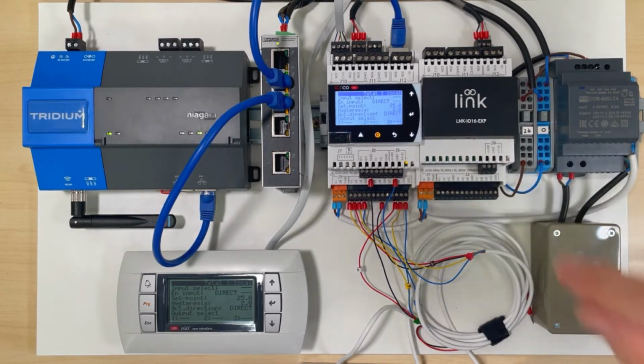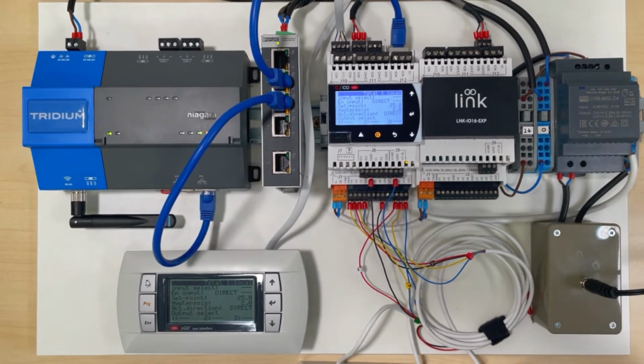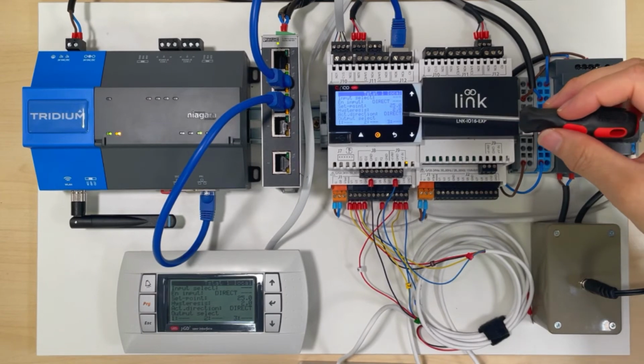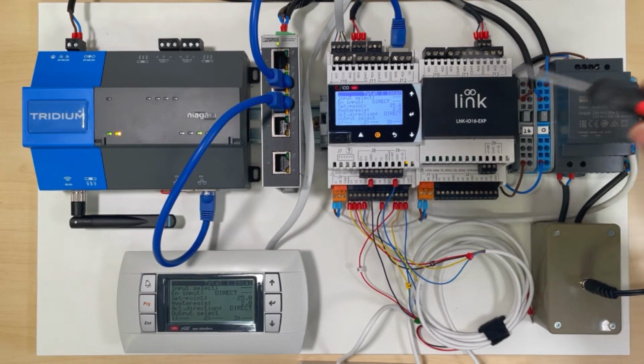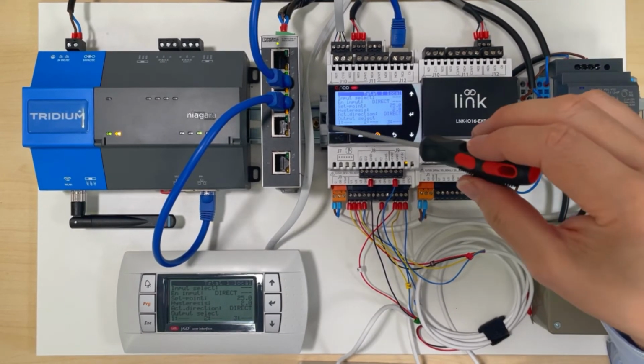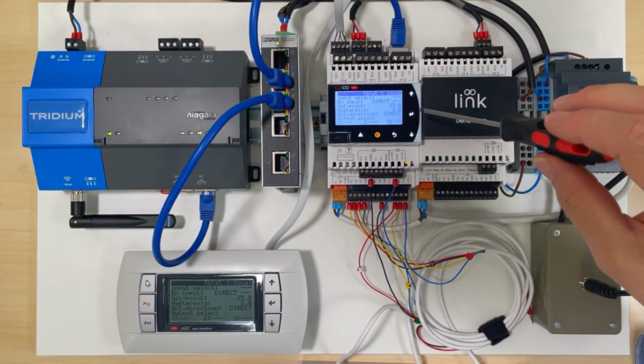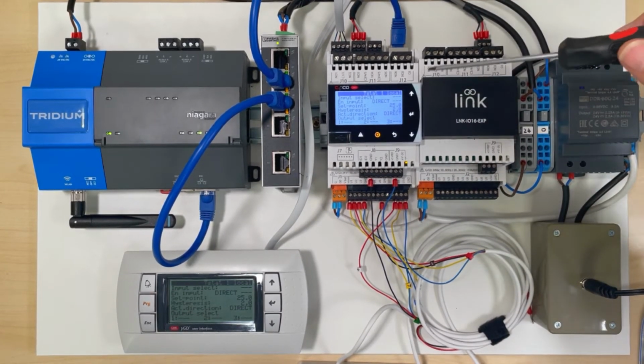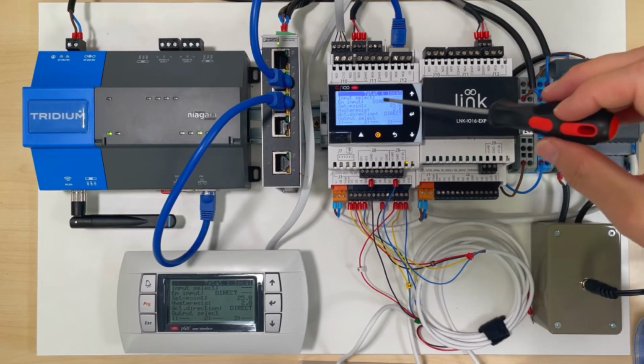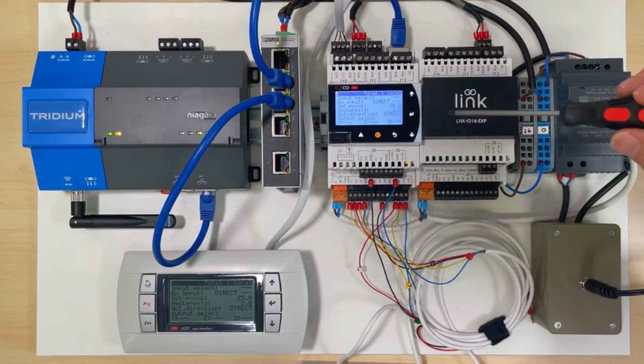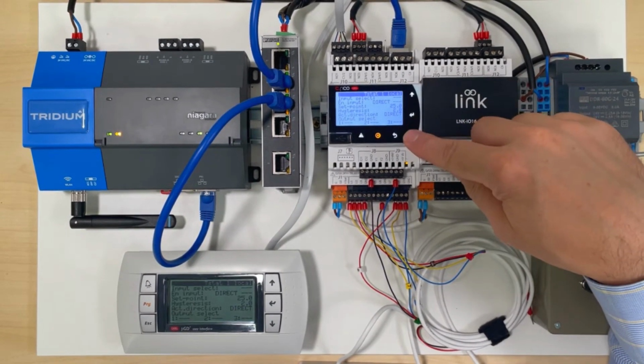Okay, there's a T-stat. So yeah, this is basic sort of thermostat action. As you can see here, you set a set point and hysteresis so it doesn't short cycle, and you can map this to up to 3 digital outputs and select, you know, like I could select that temperature sensor on universal input 1, and that could be used to control up to 3 digital outputs. 2 of those as well.